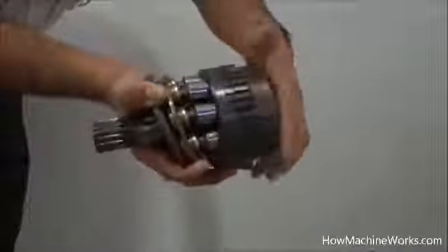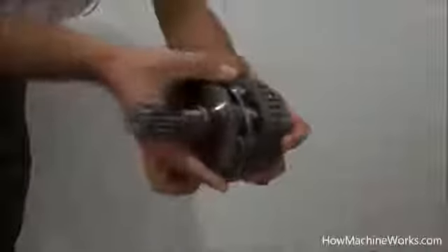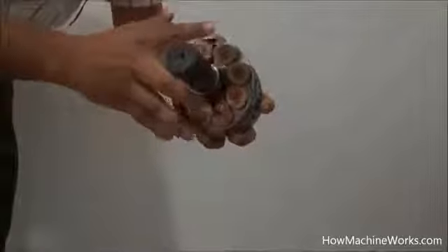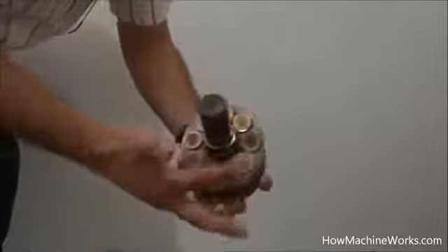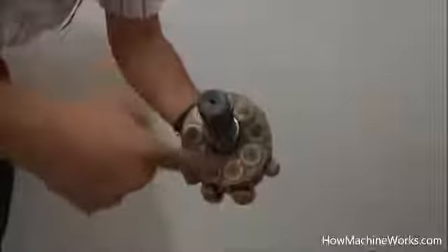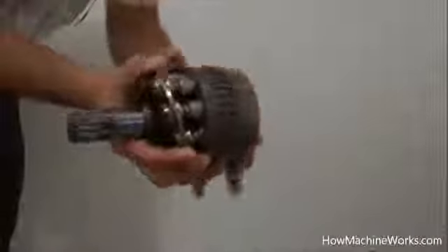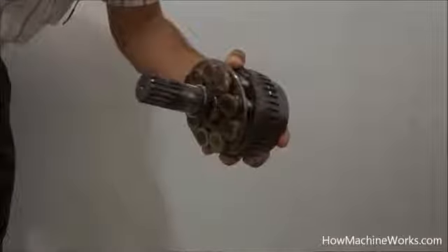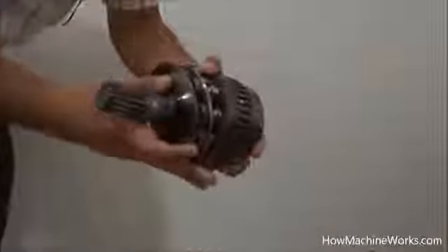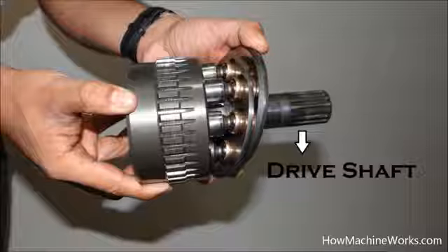So when the swash plate is vertical, there is no flow, and as the swash plate angle changes, the flow varies depending upon the angle of the swash plate, and the swash plate angle is controlled by a valve according to the load and the requirement. So that's the rear side of the piston which is sliding over the swash plate over there. Okay, now let's go and have a closer look and identify each component over there.